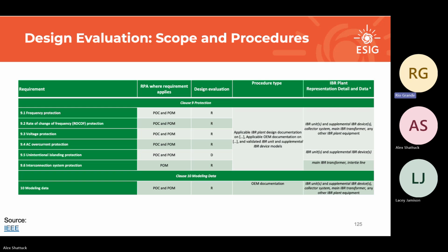These types of protections almost never modeled in the PSPD. They're more often modeled in the EMT, if modeled at all, but they're going to be very important. There's a good reason why they're mostly ignored because rate of change of frequency was never super high, but now the grid's weakening, RoCoF is going up, and now we see more often those protections actually activating. So testing those, make sure they're doing what they're supposed to do and actually aren't overly constraining is super important.